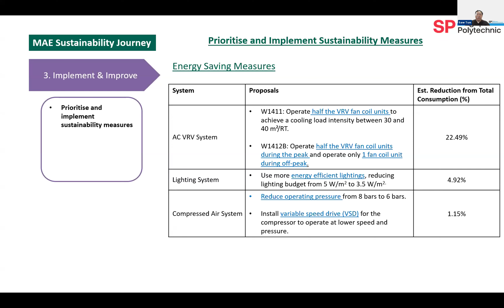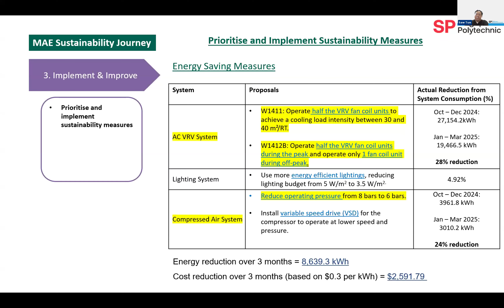Next slide, I would like to share our results for the past 3 months. Since January 2025, we have implemented these energy-saving measures in our workshops. By comparing 3 months of data before and after the implementation, we observe a 28% reduction in energy consumption for the air conditioning systems, achieved through the behavioral and operational changes. Similarly, the compressed air system saw a 24% reduction by lowering the operating pressure from 8 bars to 6 bars. Overall, for the 3 months, we managed to save more than 8,600 kilowatt hours.